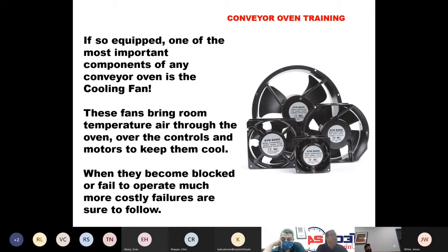One of the most important things in a conveyor oven, if it's equipped, is the cooling fan. These fans are used to bring room temperature air through the oven over the controls and motors to keep them cool. If they become blocked or fail to operate, you can have much more costly failures. Anytime you're working on any oven that has cooling fans, which is pretty much all of them, make sure the covers are clean, make sure that the fans are operating correctly. The fans are always going to be bringing air in from the outside and pushing it into the oven. It is not uncommon for technicians to install a fan in the improper direction.